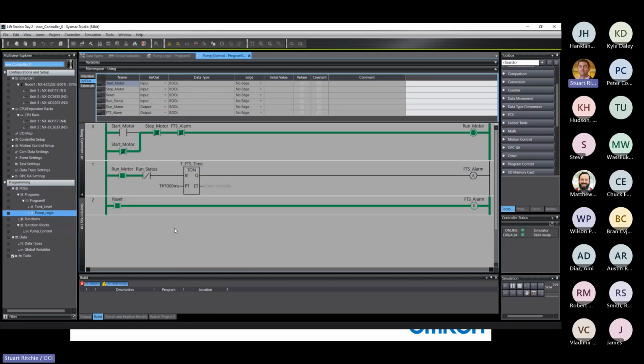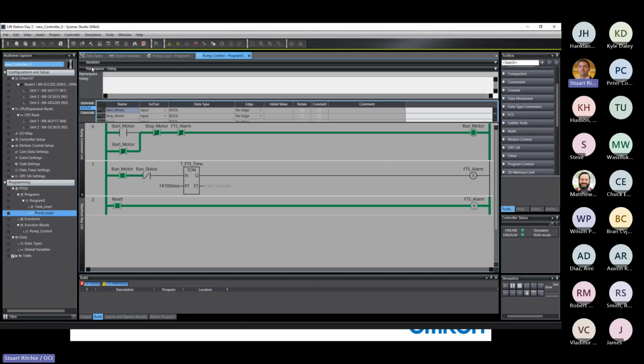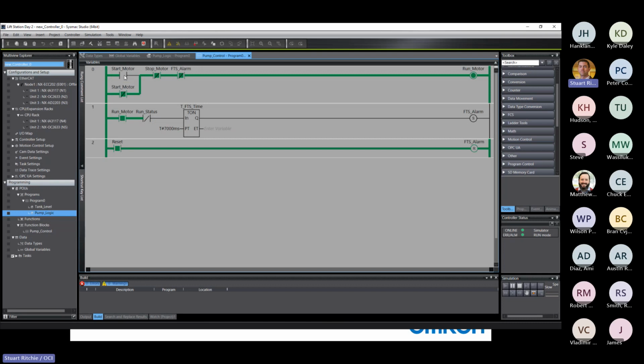We can have countless instances of this function block, and we can look in a specific instance of it. Okay, now somebody pointed out the bug earlier, and it looks like instead of making a latching variable, we made a start motor normally closed when it should be a run motor normally open. So we can edit our function blocks online, both in the simulator and on the PLC.